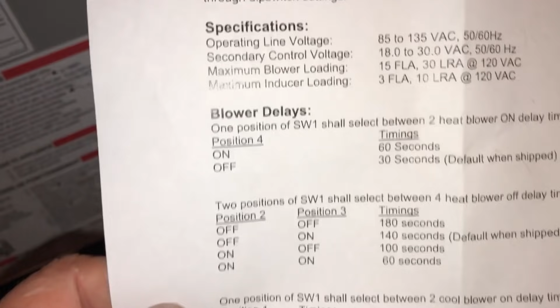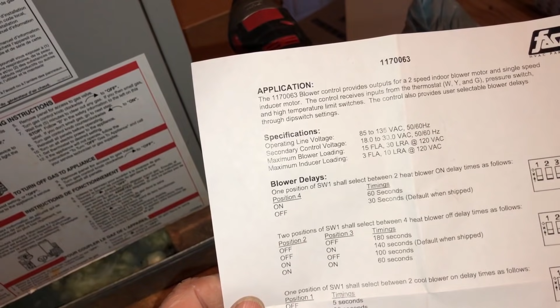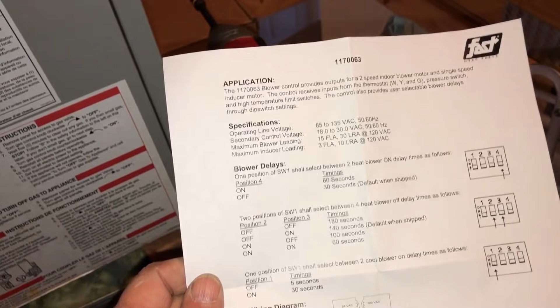Now, of course, another thing you can do before you leave these is the dip switches. It gives you several different options here for blower delays, the on and off delay. Good to have a little bit of delay after the heating cycle, kind of clear the heat off of it, cool the heat exchanger down. Some people like the delay on cooling and delay on heating, they decide there's certain ways they like all that. I don't get too wrapped up in that on the old simple furnaces. They're okay with me, whatever they want to do, but we'll watch it and make sure we like it. So let's fire it up.